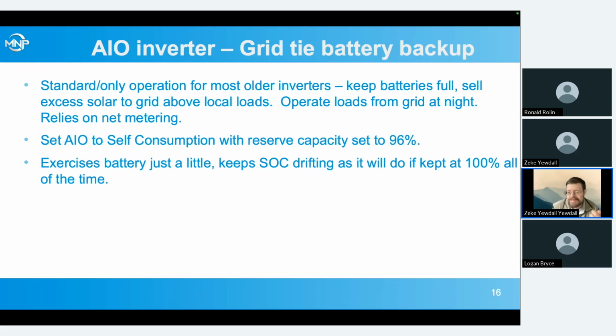And it says, I'm at 96%, I need a top off charge. And it does a top off charge. It goes through its little recalibration when it hits 100%. And it keeps that state of charge drifting from happening by dropping it down and then recharging it each day. So this is why I prefer this rather than setting that reserve capacity to 100%.